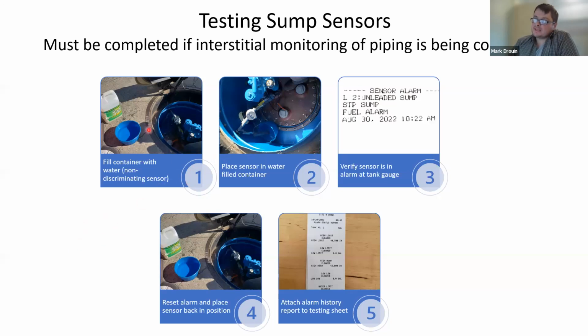You would place this sensor in testing fluid, they call it. We used water because this is a non-discriminating sensor. Keep in mind, if you have what's called a discriminating sensor, you want to test it per that fluid. So if this is an unleaded tank with regular fuel and it's a discriminating sensor, that has to be fuel basically for the testing.